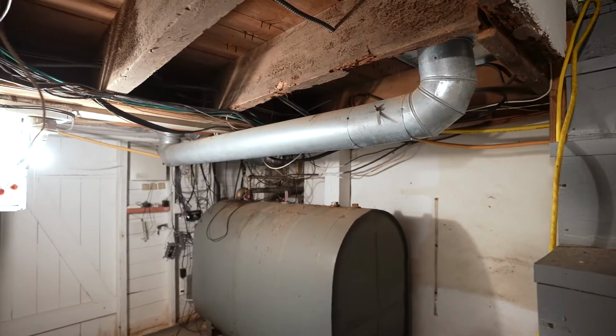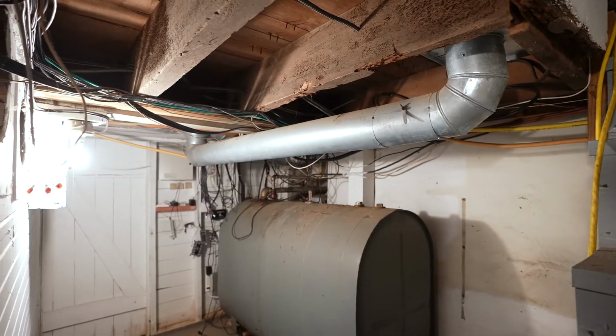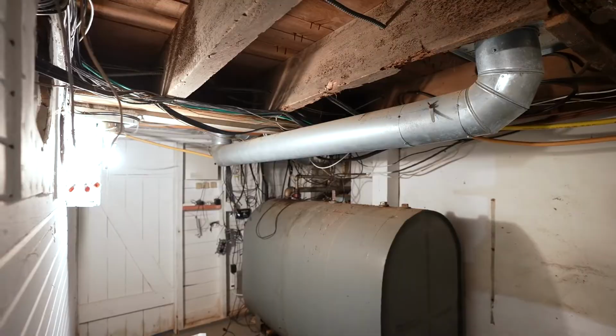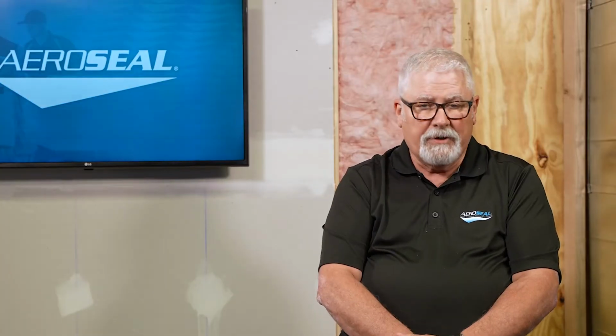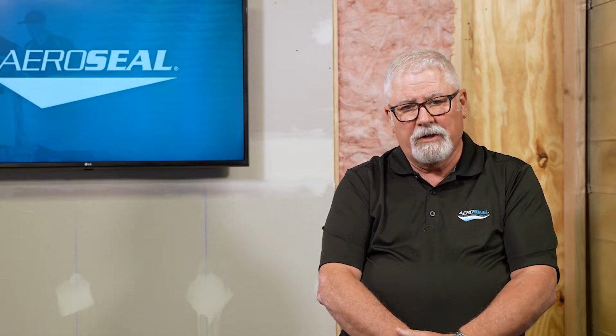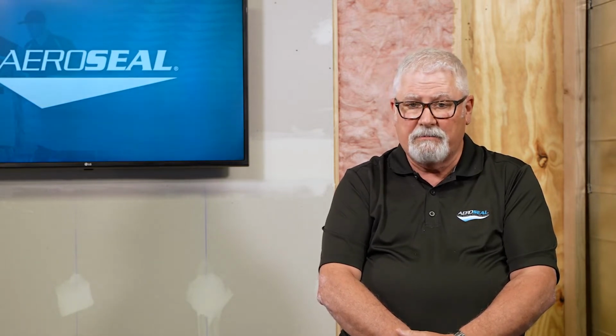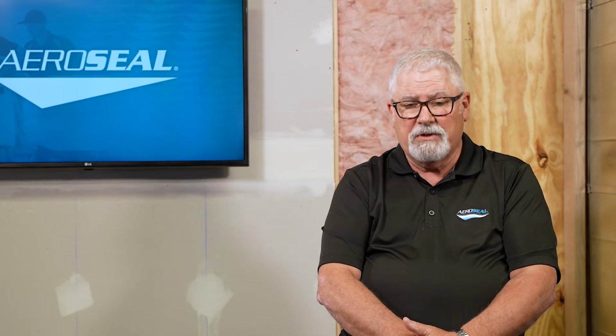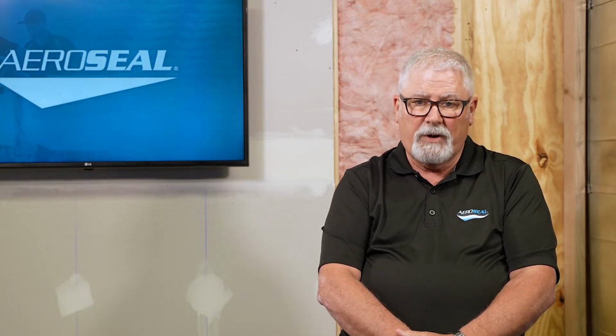This can backdraft gas appliances, such as a naturally aspirated water heater, or maybe a gas furnace. In some cases it can also pull air in from outside in the summertime, bringing a lot of heat and, more importantly, humidity into the basement, which can cause humidity issues upstairs and make ductwork sweat.